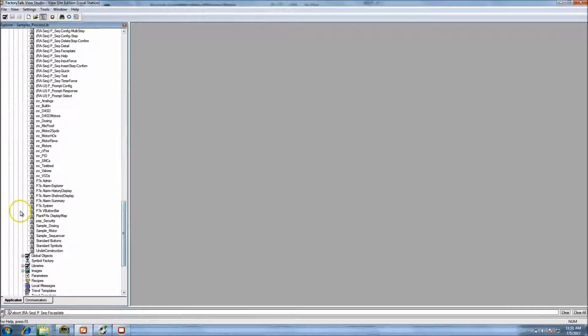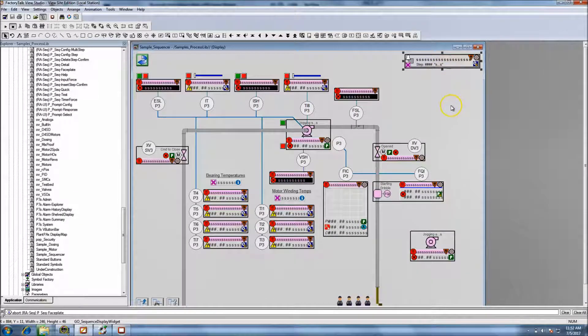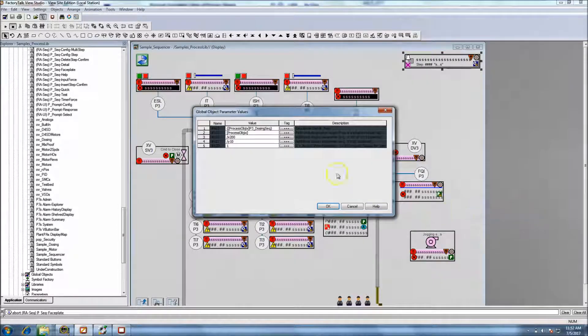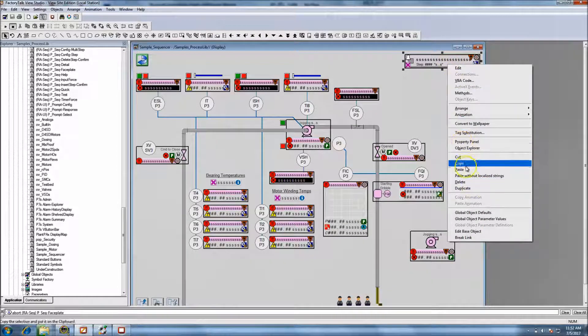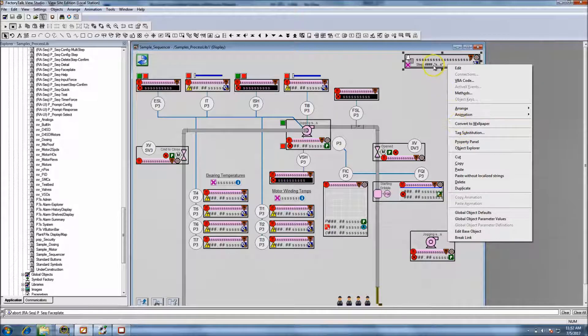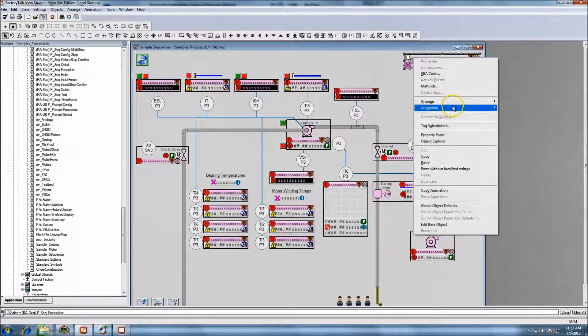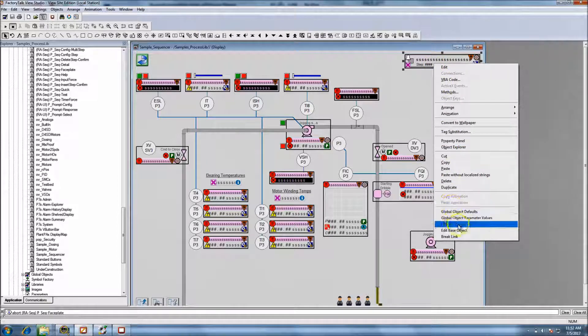We go to all of our displays, come down and find our sample sequencer, open the screen up. This is exactly the screen that shows - it's a global object, so we have to treat it like that. We can look at global object parameters and see exactly what's being preloaded into this button. When it's pressed it's calling another screen. You can look at animation and tag substitution but you can't really get to it because it's a global object.